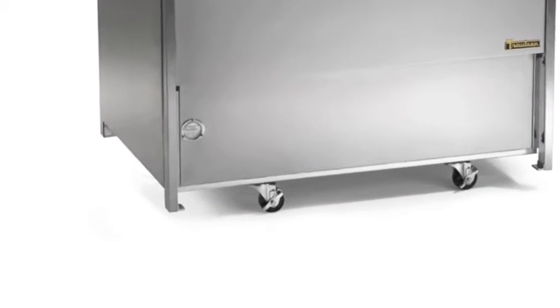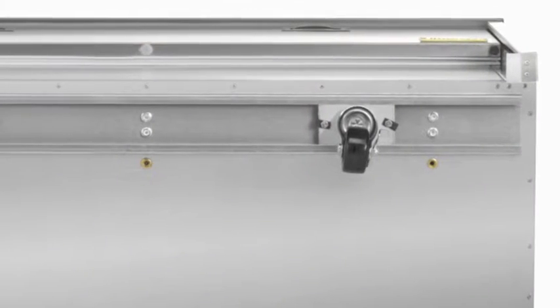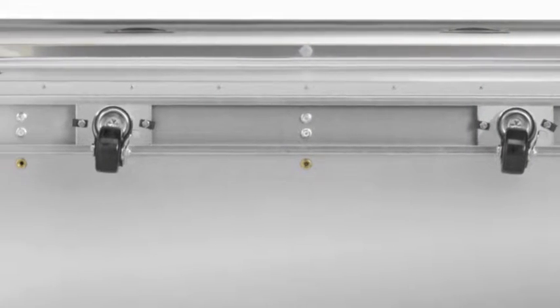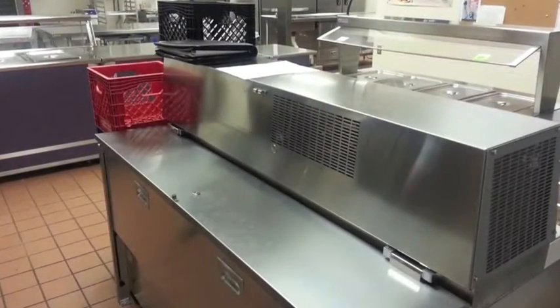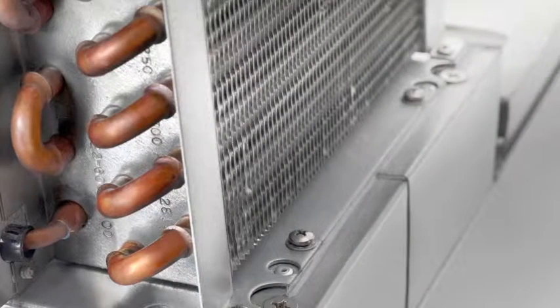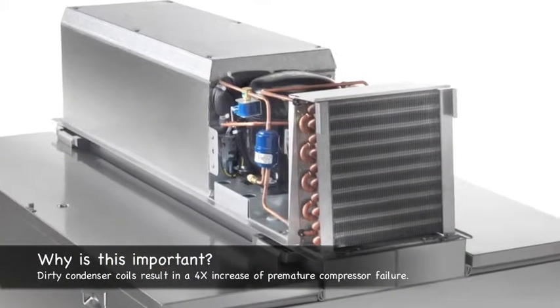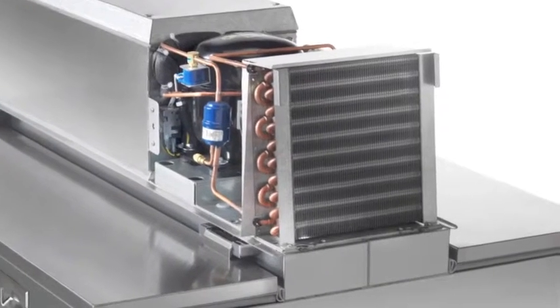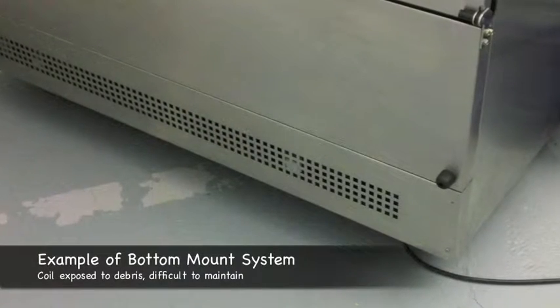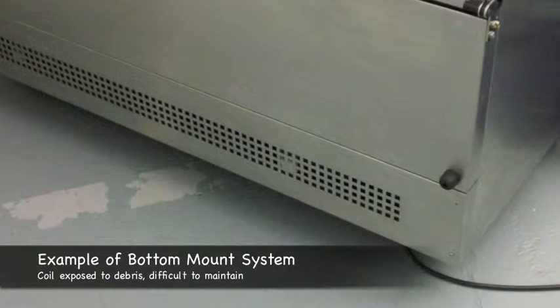Installation is made easy thanks to Traulsen's full-length caster channel. This allows the casters to be easily adjusted left or right, out of the way of obstructions such as floor drains. Your maintenance people are going to love the top-mounted system design, because cleaning the condenser coil is critically important to promote efficient operation and maximize compressor life. By locating this on top, it is not only easier to clean, but will also not accumulate nearly as much dirt and debris as those of other brands placed near the bottom, where they are exposed to debris every time you sweep the floor.